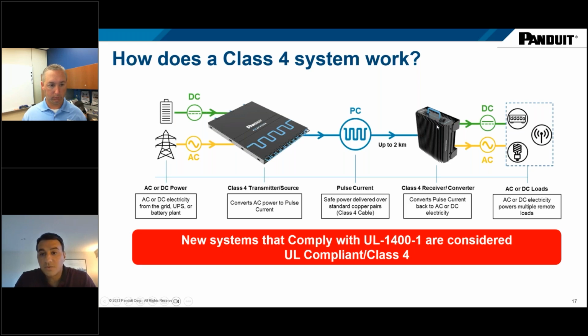And then from the converter, it will rectify that power and provide either DC or AC to the end loads. One thing to really highlight here is that there are no class 4 systems out in the market yet. UL just published that new standard, and new systems that come up and comply with UL 1400-1 will be the only ones really considered to be class 4.